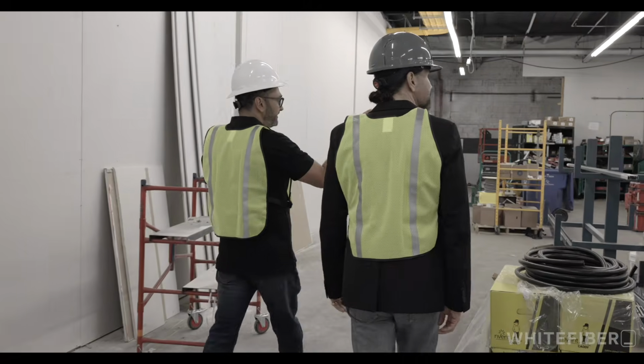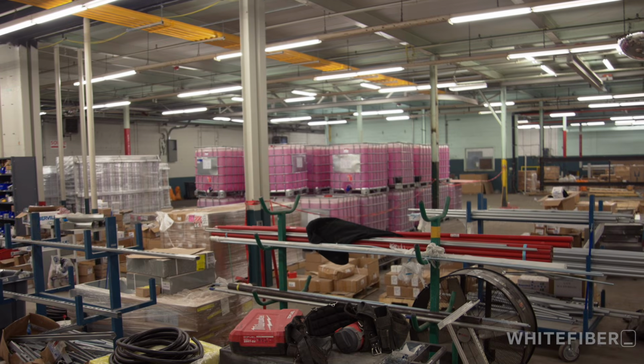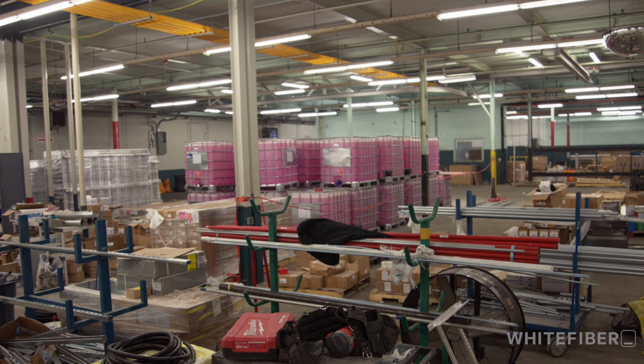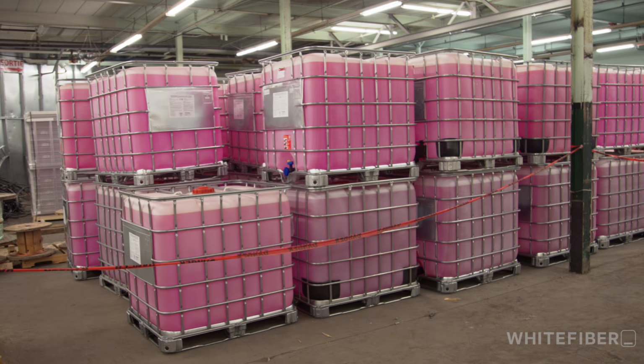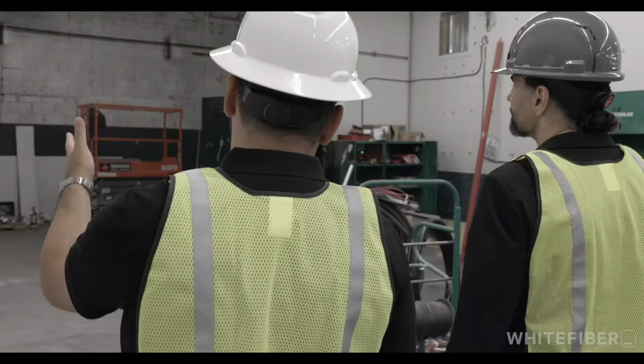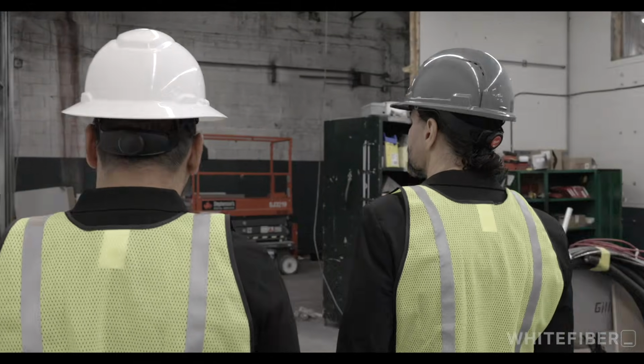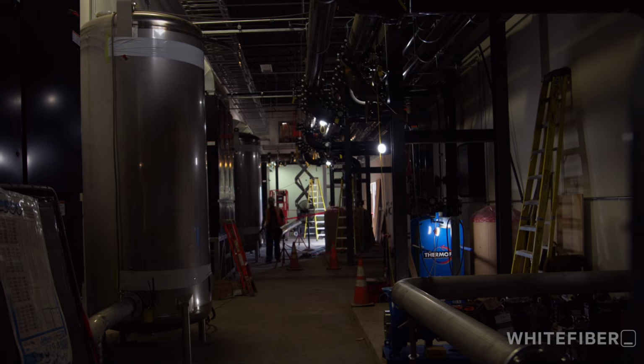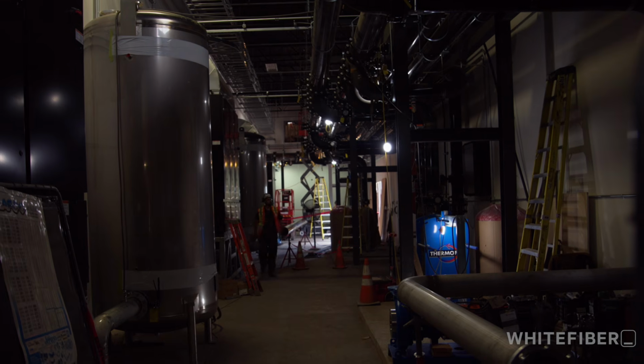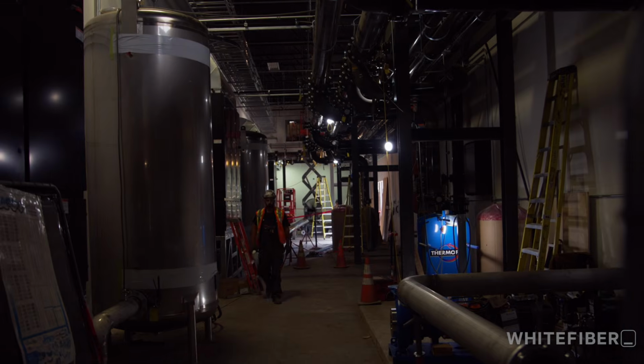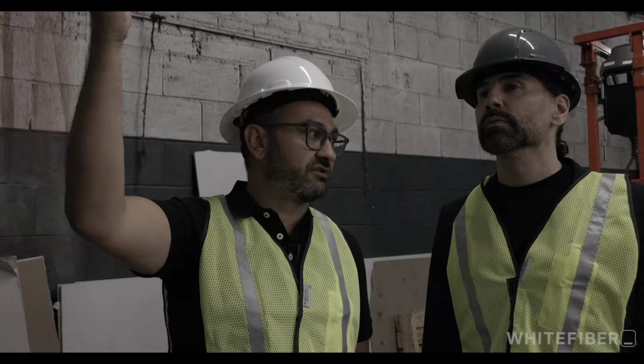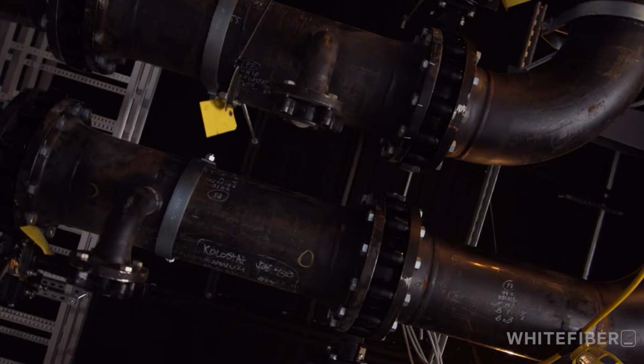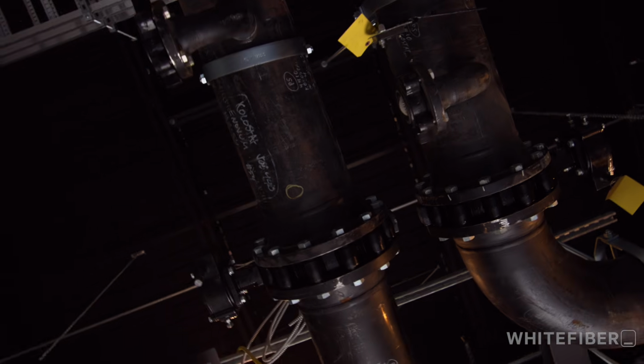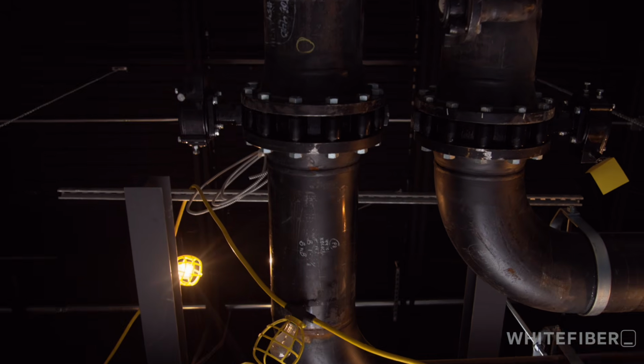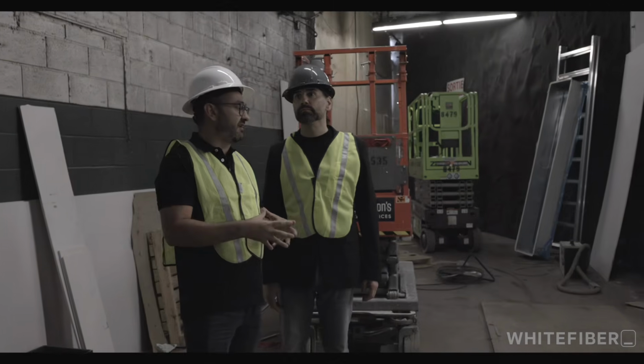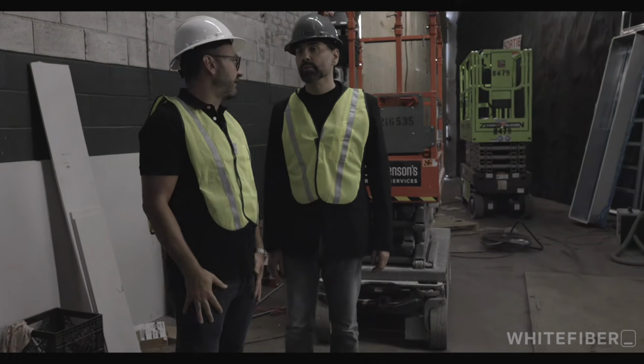Over here we have the glycol that goes into the glycol portion of the cooling loop. This site is a direct-to-chip liquid-cooled site. We're coming up on the mechanical gallery, where we have all the mechanical equipment, including the air handlers for the white space and the pumps that move chilled water to the customer's equipment. It's a very complicated system, fully redundant. Any one portion of this system can be removed and the customer is still up and running.